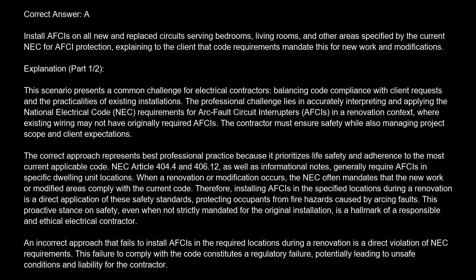The correct approach represents best professional practice because it prioritizes life safety and adherence to the most current applicable code. NEC Article 404.4 and 406.12, as well as informational notes, generally require AFCI in specific dwelling unit locations. When a renovation or modification occurs, the NEC often mandates that the new work or modified areas comply with the current code. Therefore, installing AFCI in the specified locations during a renovation is a direct application of these safety standards, protecting occupants from fire hazards caused by arcing faults.